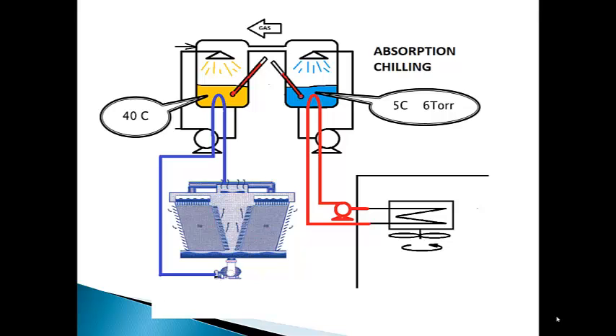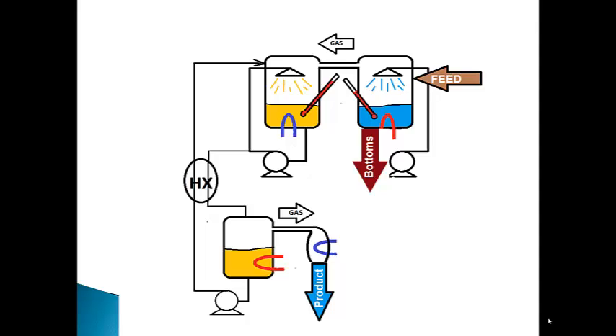The absorber also operates at 6 torr but at a much higher temperature, typically 40 degrees Celsius. At this temperature, heat can be removed from the absorber with ordinary plant cooling water, furnished by evaporative cooling towers. So our little thought experiment has led us to the rediscovery of the absorption chiller. But I would like to take us one step backwards, before we closed the water circuit. What if we fed the evaporator with an externally supplied stream of slightly contaminated water, removed a bottom stream from the evaporator, and took a stream of distilled water as product from the condenser? What would you call such a process?